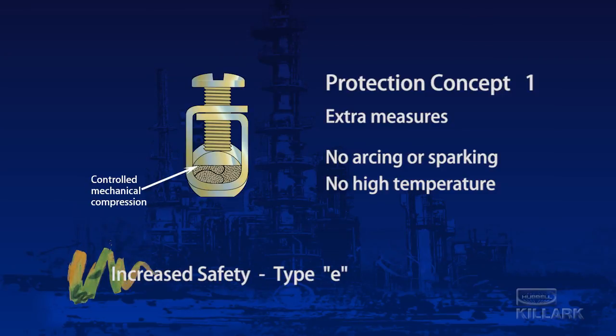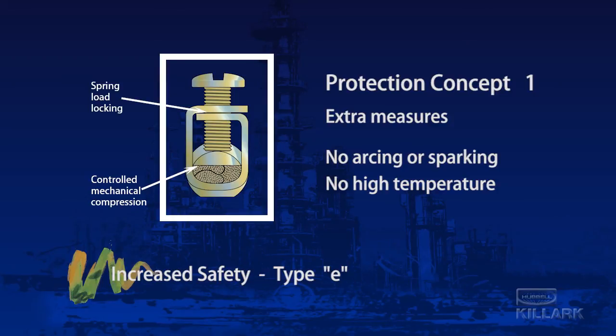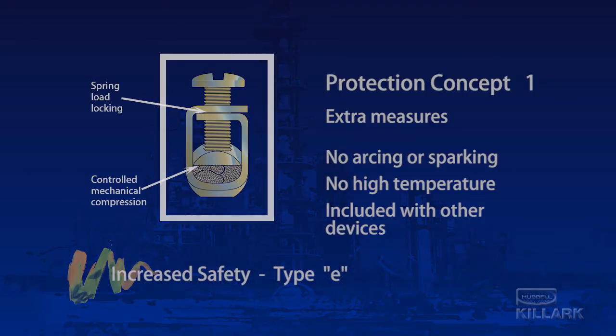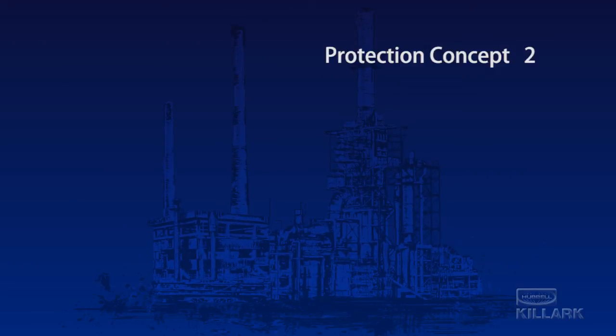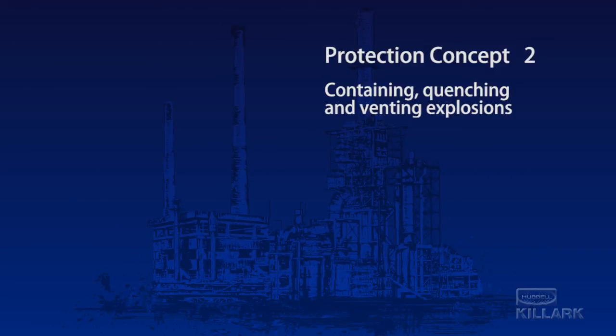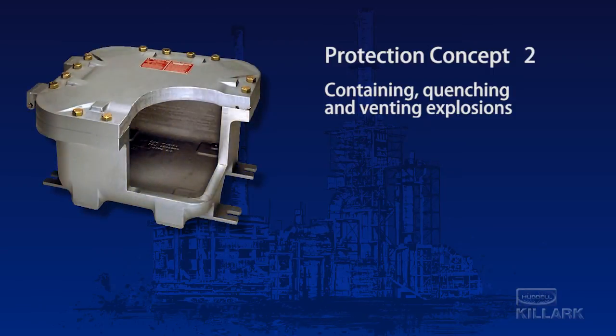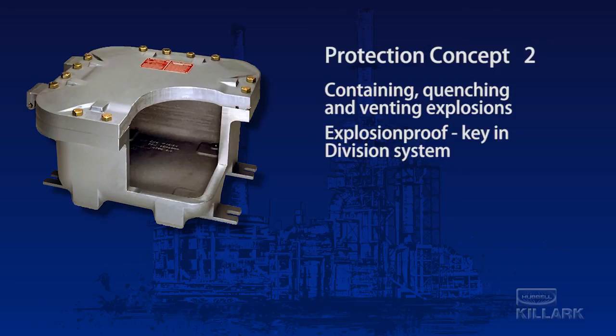The use of additional clearances, spring-loaded terminations, and physical protection provide a method that can be applied to standalone terminal and connection boxes, or in conjunction with other methods, such as those used for controls, motors, and lighting fixtures. Another approach has been developed around the concept of containing, quenching, and safely venting explosions that could occur when ignitable mixtures come in contact with arcing or high-temperature equipment. This concept includes explosion-proof enclosures, a major technique used in the division system.